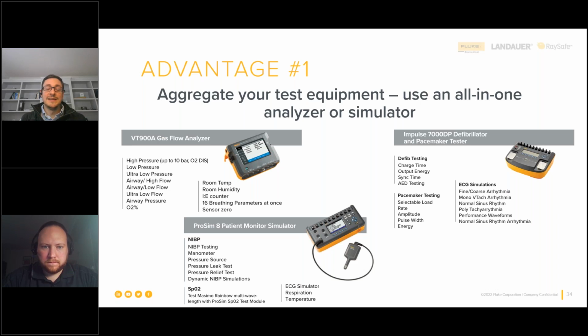The ProSim can replace any standalone NIBP monitors, but it also does IBP. It has an ECG simulator, an SpO2 functional tester, all of that in one box. Impulse is another one. It combines defib testing, pacemaker testing, and ECG simulation in a single box. Would that help you improve your workflow? Think about calibration. It's not just carrying less, it's calibrating less. So there's no need to deal with multiple vendors when you do that. When you have different functional testers, you have one. It goes out for one calibration, it comes back with one report, it comes back with one price. So do let that be a factor in your decision as well. So combining functionality can help you carry less. It can help you calibrate less. So if your facility is willing to invest, if your facility does have that growth mindset, these might be great products to look towards, leaning on and making that happen for your organization.